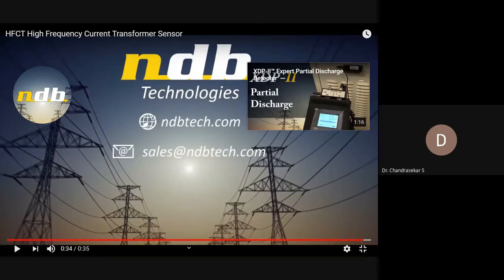Yeah. So now, as I already told, the calibration of these high frequency current transformer sensors, particularly for high voltage applications, is very, very important. Whether we are really measuring partial discharge or any other signal is really a big challenging task. Why I am telling this is, this HFCT sensor will capture all the signals which are available in the surrounding area.